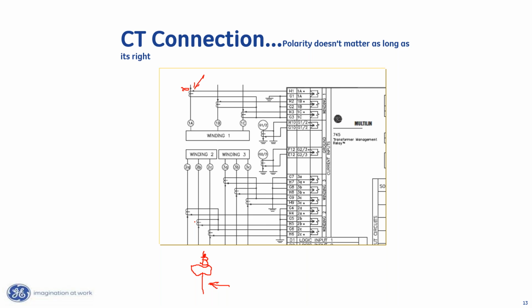I've seen people wire things incorrectly because they always felt like they needed to wire polarity on the relay to polarity on the CT. And in this case, that'd be a problem, right? Because we've got current flowing here. If that's flowing there, that means it's flowing into polarity on the relay. We've got current flowing here, which means it's flowing out of the polarity on the relay. Now, if we use this same set of CTs and wired polarity here, current would be flowing into polarity. So if we were comparing this current with that current, we'd have a problem. So we need to wire it down here so that it would be flowing out of polarity, or at 180 degrees. So polarity doesn't matter as long as it's right.